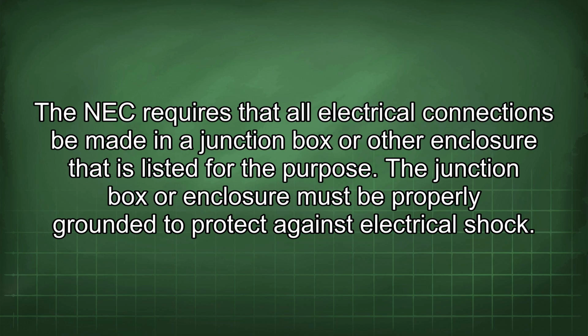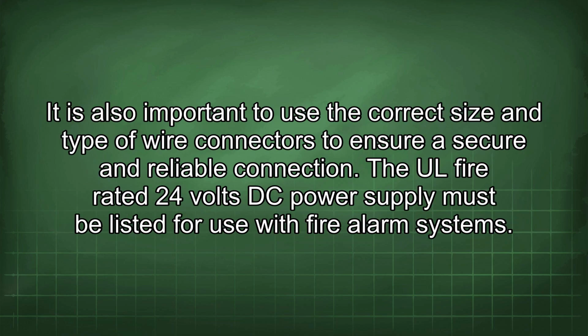The NEC requires that all electrical connections be made in a junction box or other enclosure that is listed for the purpose. The junction box or enclosure must be properly grounded to protect against electrical shock. It is also important to use the correct size and type of wire connectors to ensure a secure and reliable connection.